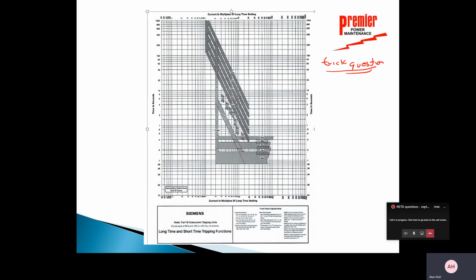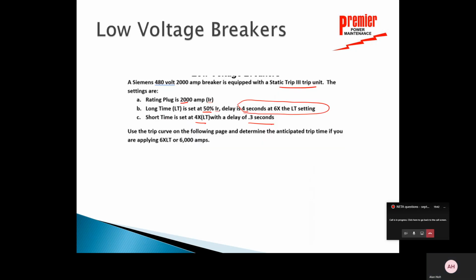So if we go back to the statement, long time set at 4 seconds at 6 times pickup. Okay, 6 times pickup. All right, that's cool. 6 times pickup would be 6,000 amps. That's exactly where I'm picking up at. I'm testing it at 6 times pickup. So your first thought is, okay, it's going to trip in 4 seconds.